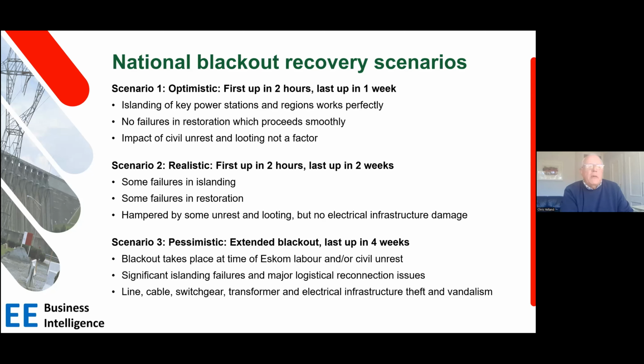I must stress this is a pessimistic scenario. It assumes there are a number of failures, things like civil unrest or a labor strike complicating matters, islanding failures where the islanding systems don't work properly, and significant theft and vandalism of line, cable, switchgear, transformer, and other electrical infrastructure, which slows the recovery process. In other words, if you've had transformer theft, failures, damage, fires, caused by unrest, it's going to take significantly longer to recover from a national blackout.